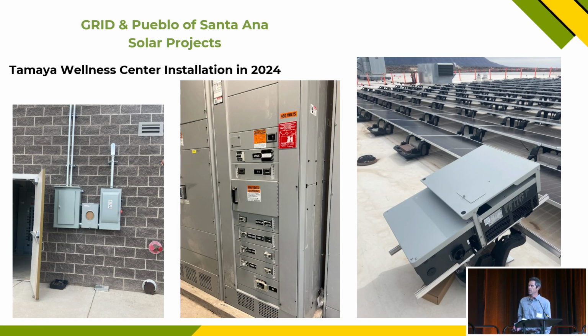A lot of these community buildings typically have backup generators, as a place people can go if the community loses power or there's a community event. Fortunately, this generator is downstream from their main service panel, so they had critical loads backed up instead of the whole electrical service. If a generator backed up their entire electrical service, we would have gone on the line side of that generator, between the utility and the generator, so the inverter and solar system aren't operational while the generator's on, to avoid conflicts. But don't want to get into the weeds there - ultimately, it was a really clean install that turned out great. Hope to have it on by the end of the month.